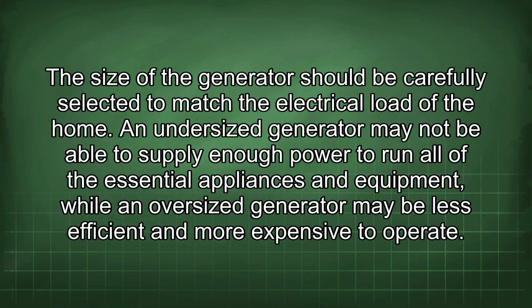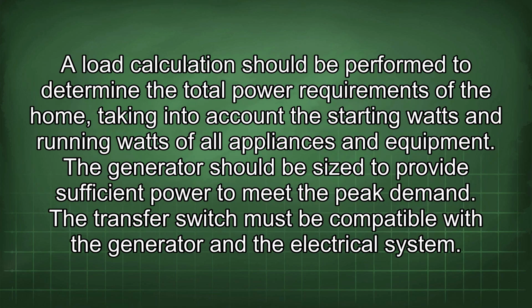The size of the generator should be carefully selected to match the electrical load of the home. An undersized generator may not be able to supply enough power to run all of the essential appliances and equipment, while an oversized generator may be less efficient and more expensive to operate. A load calculation should be performed to determine the total power requirements of the home, taking into account the starting watts and running watts of all appliances and equipment. The generator should be sized to provide sufficient power to meet the peak demand.